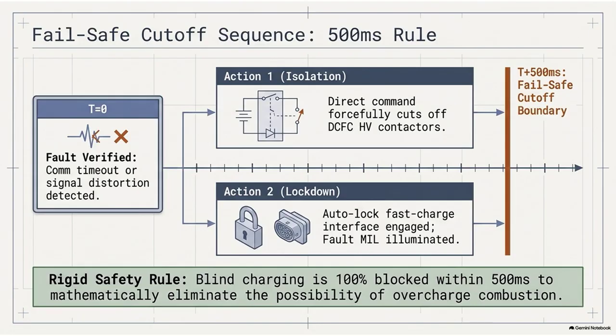But I have a fundamental question about that timeline. You say 500 milliseconds is the maximum time to prevent a fire. To a human, half a second is incredibly fast, that's a blink of an eye. But in computing, where processors operate in nanoseconds and do complex polynomial division hundreds of times a second, 500 milliseconds is an absolute eternity. The computer knows the signal is dead in 1 millisecond, so why wait half a second? Why not snap the contactors open in 10 milliseconds, the exact moment a single CRC checksum fails?